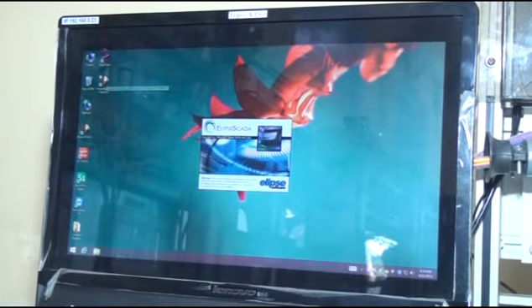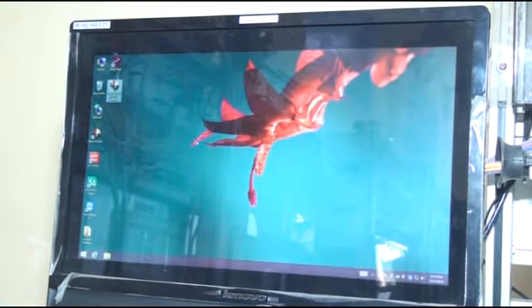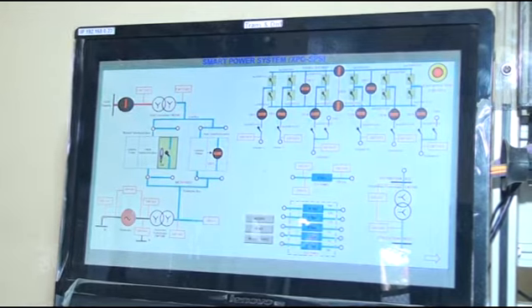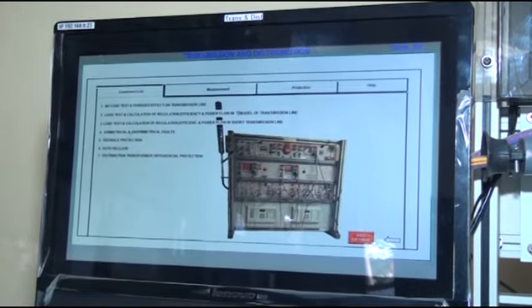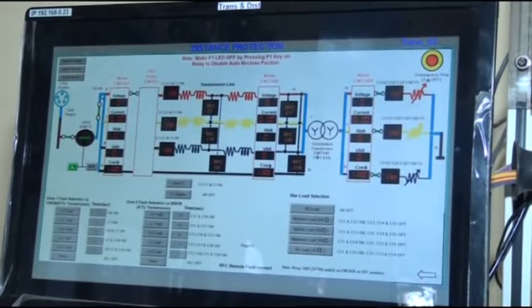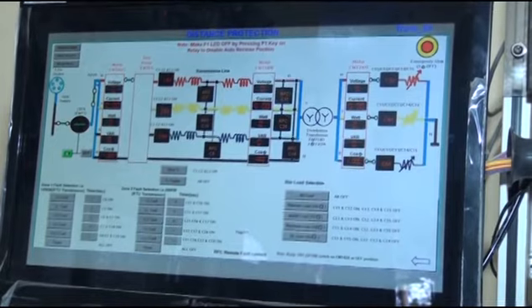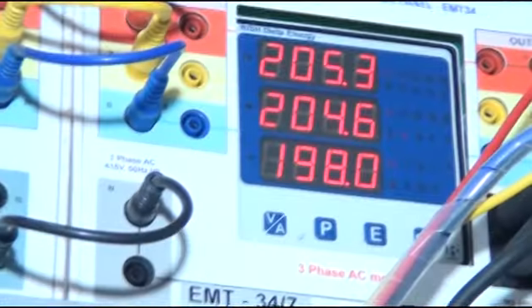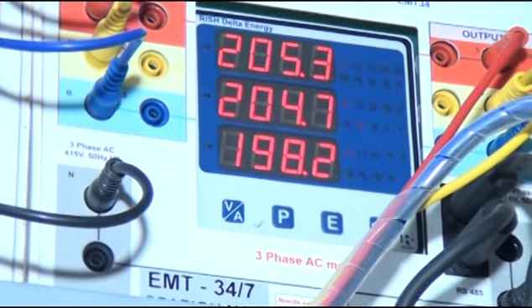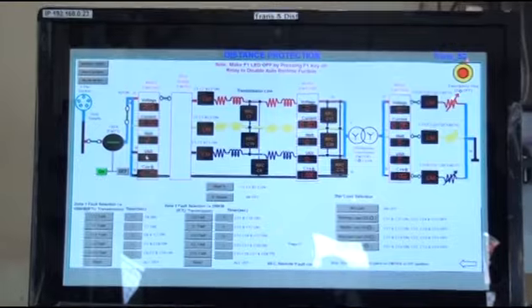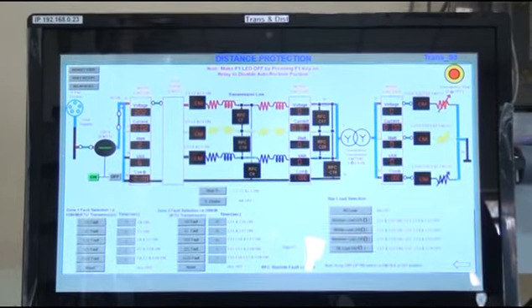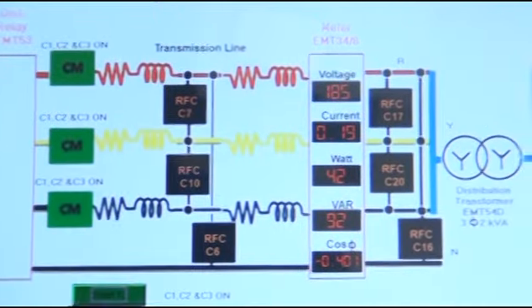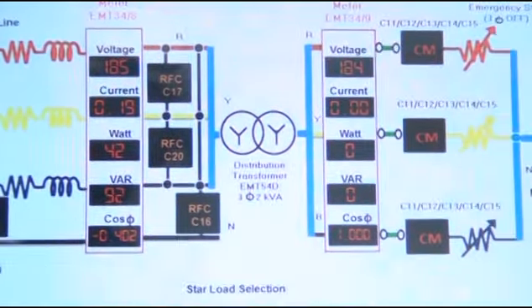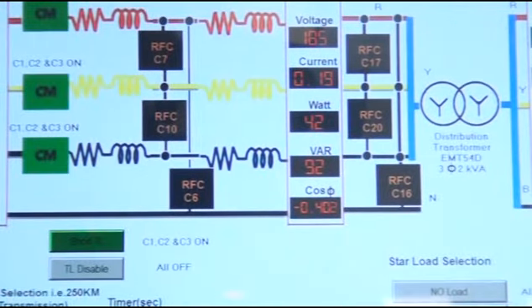Now we are performing an experiment for distance protection on the transmission and distribution setup. Open the SCADA screen and select experiment number 5, distance protection. Now switch on the input supply by making CB19 on. Observe that EMT 34 by 7, the sending end meters, show voltages and currents. Now press the short TL button on the SCADA screen to select the short transmission line. Then observe the receiving end voltages and currents at EMT 34 by 8 using the touch screen.